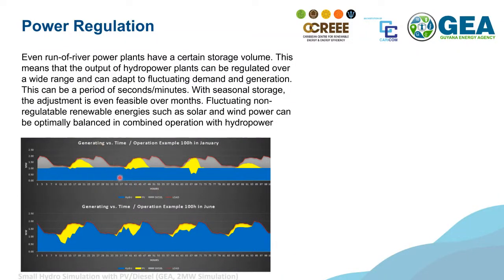We have 4 days of simulation here, one in the rainy season, one in the dry season. Starting with the rainy season: this is the hydropower, and the red line is the load of the city, going up at daytime and down at nighttime. In the first hours, the hydropower is exactly meeting the demand of the load, adapting to it. We have 2 megawatts available at this point, but the hydropower is just giving as much as is needed at the moment.